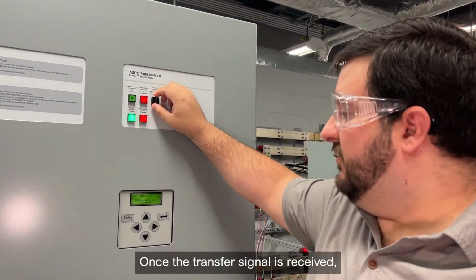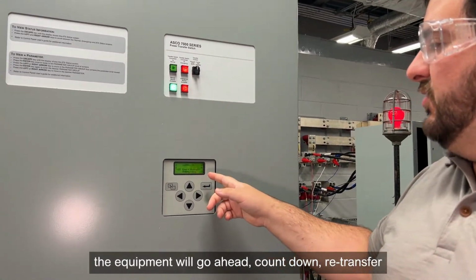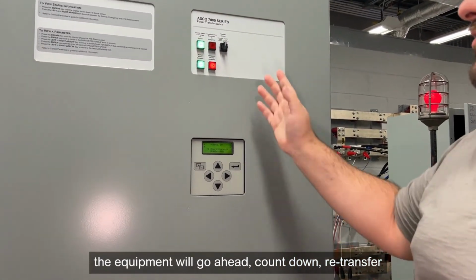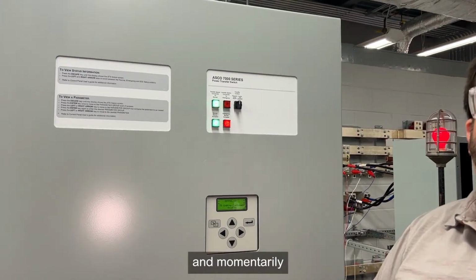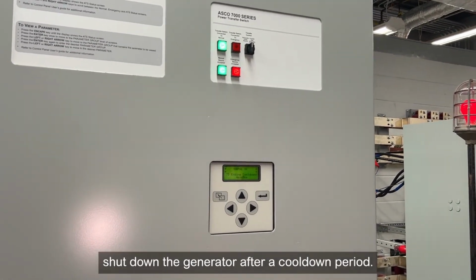Once the transfer signal is received, the equipment will go ahead, count down, retransfer to the utility source, and momentarily shut down the generator after a cool down period.